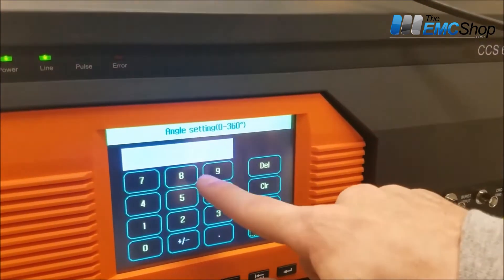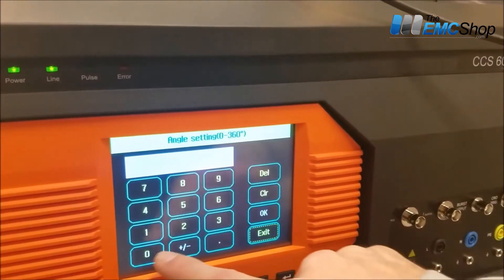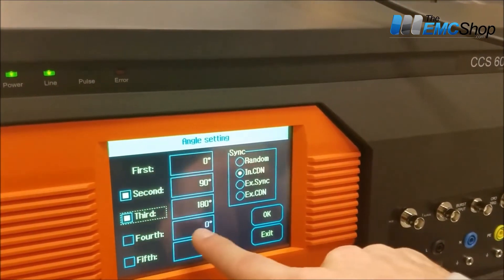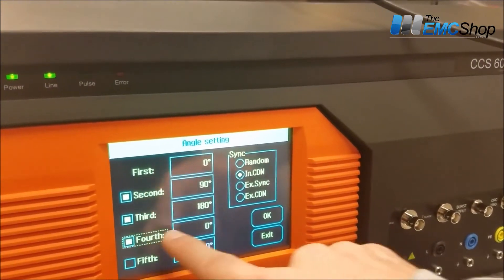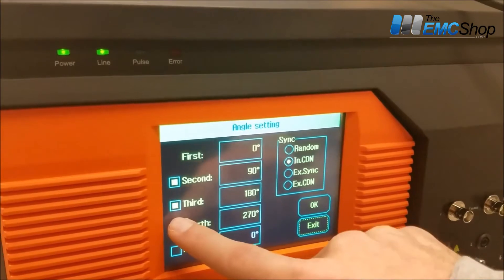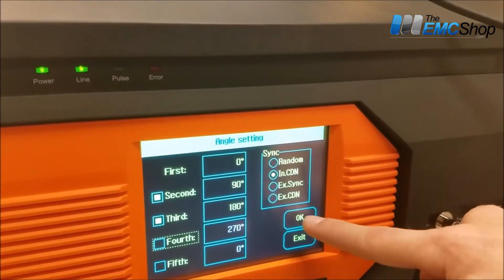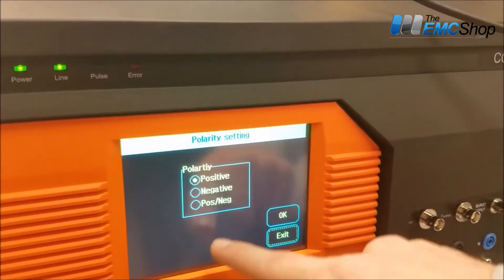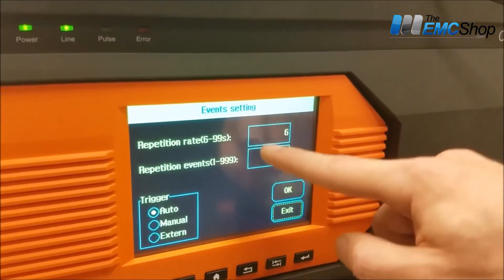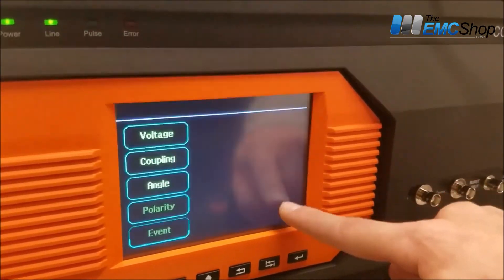Angle — you can adjust the angle if you want to apply the surge at 90 degrees. Or if you're doing a normal test, you can step through each phase. Make sure In.CDN is selected. Polarity is straightforward. Repetition timing — I'm just doing a quick test, so I set it up pretty low for now.